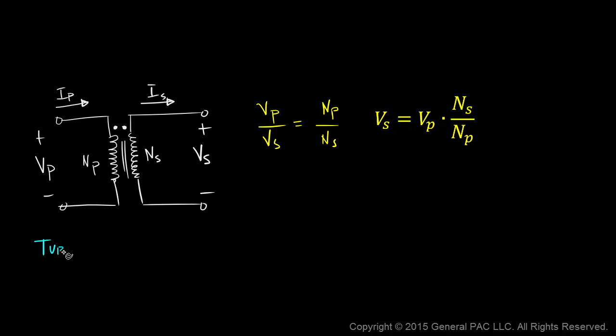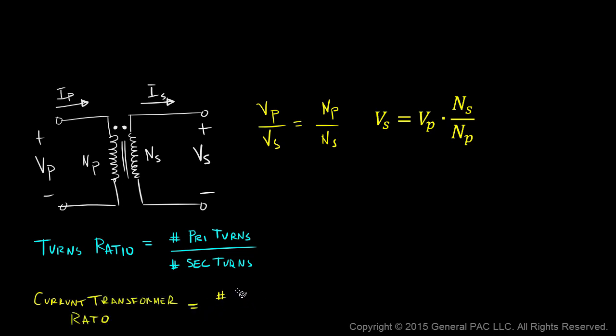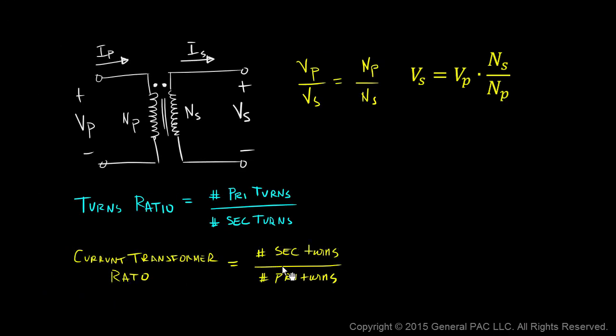The turns ratio in a transformer is defined as the number of primary turns divided by the number of secondary turns. But when talking about a current transformer, the CT ratio is a little bit different — it equals the number of secondary turns divided by the number of primary turns, which is essentially flipped. Why is it flipped? Let's try to understand this intuitively.